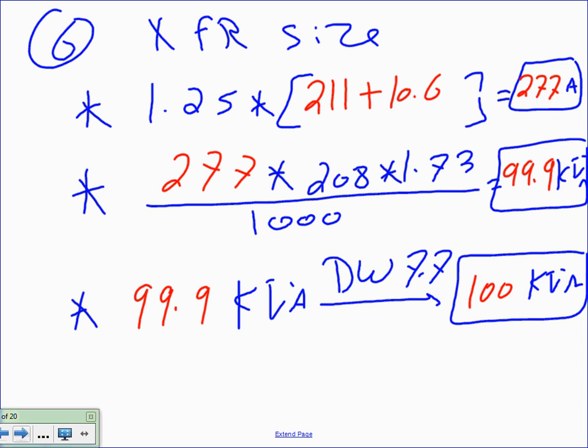Where do I find the standard 3-phase 480 208 transformers? It's not enough, guys, to do the math for us. We are required to put actual material. Actual material is in the DeWalt 7-7, or you can use the Cutler-Hammer Consultant. Beautiful consulting guide, Cutler-Hammer. If you work in an engineering firm or high-profile electrical contractor and you don't have this one in front of you, you deserve a horse whipping. That's a big deal if you want to get into design.